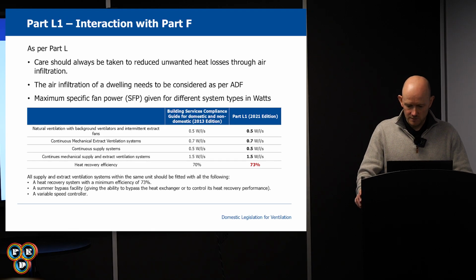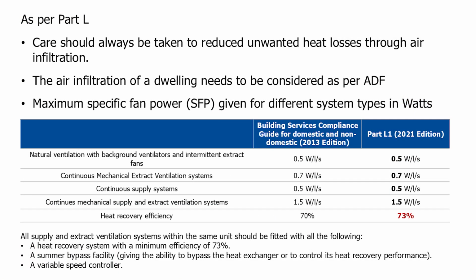Mechanical ventilation systems in regards to approved document L are largely unchanged, but continue to specify that systems should be designed to minimise electric fan power, which is called specific fan power, and should not be worse than shown in the table. Specific fan power is calculated by dividing the wattage of the fan by the duty rate in litres to give you the watts per litre rate. The only change here is the heat recovery efficiency, which was originally stated to be a minimum of 70% within a building services compliance guide, and is now 73% as of 2021. Just for your knowledge, 73% is achieved by every manufacturer's heat recovery system, so everyone far exceeds that.